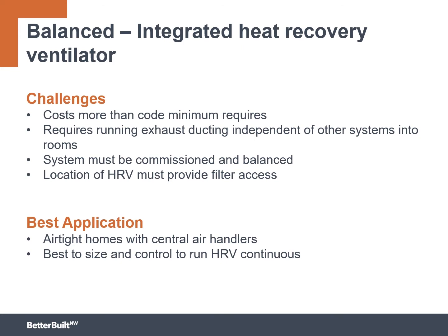And this is where it gets really challenging. System commissioning and balancing when you're integrating into a central air handler can be pretty challenging. You need to have a good order of operations for how you commission the entire HVAC system, including the heat recovery ventilator. And it's going to be really critical and can be a little challenging. So there's a bit of a learning curve for this strategy for most builders and HVAC trades.